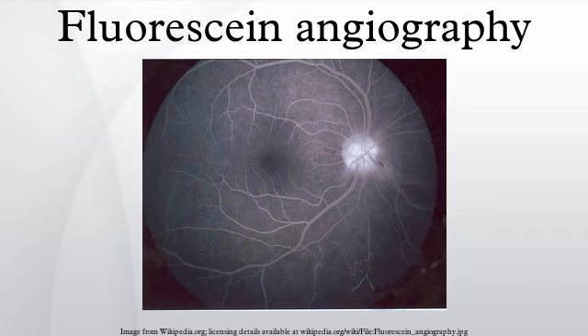Fluorescein angiography does not involve the use of ionizing radiation. Regarding equipment: the exciter filter allows only blue light to illuminate the retina. Depending on the specific filter, the excitation wavelength hitting the retina will be between 465 to 490 nanometers.